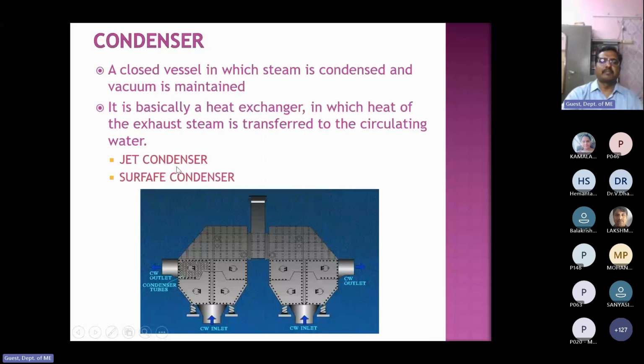In a jet condenser, steam which is coming from the LP turbine is directly mixed with cold water. Cold water means already water. So when it is directly mixing, the heat energy is directly taken by the cold water. This is used for very small turbines where there is no reutilization of water. This is the jet condenser. But a surface condenser is an indirect contact type exchanger.